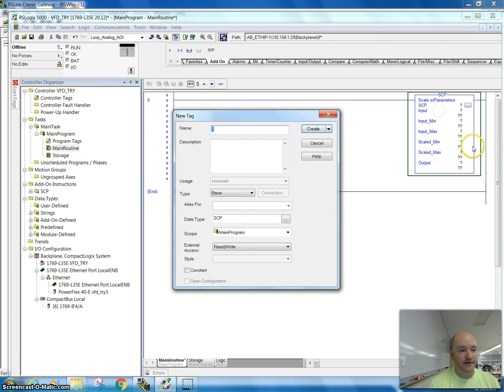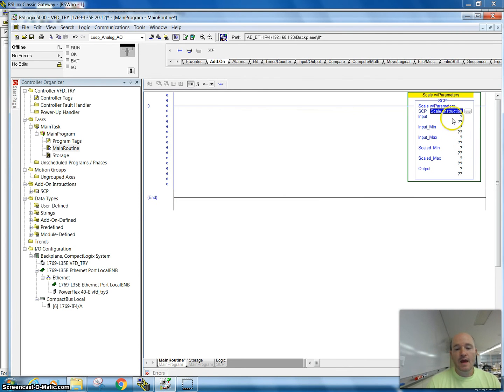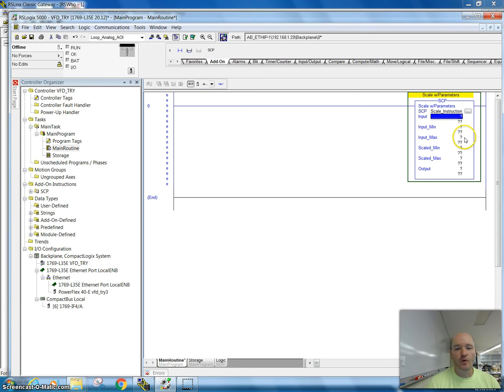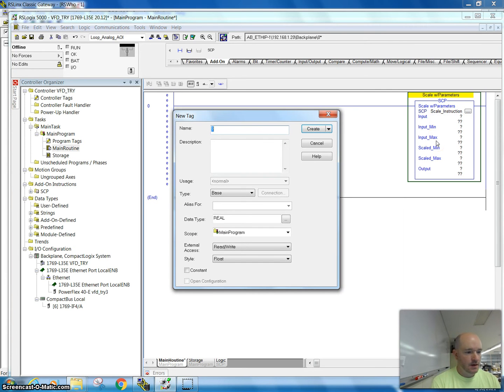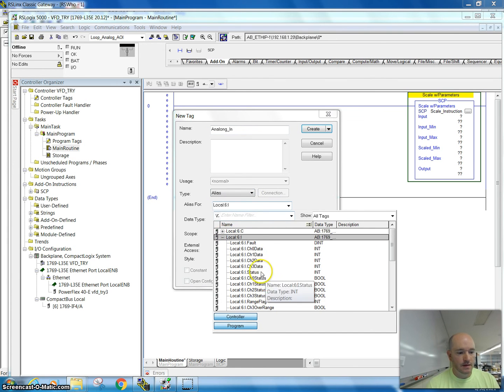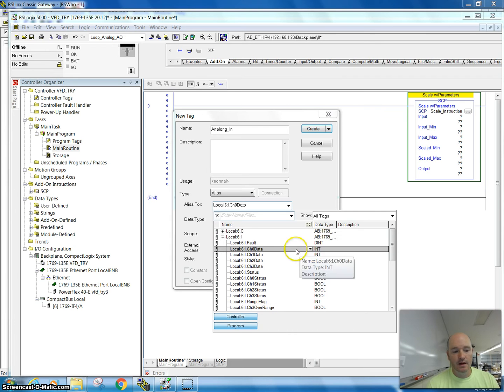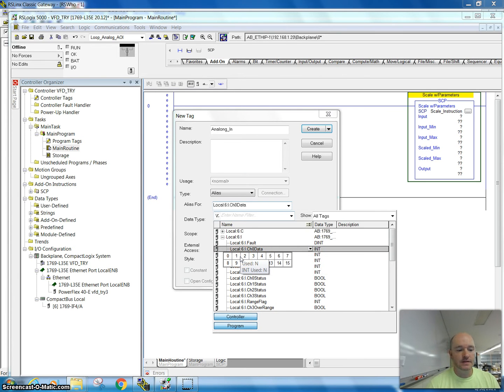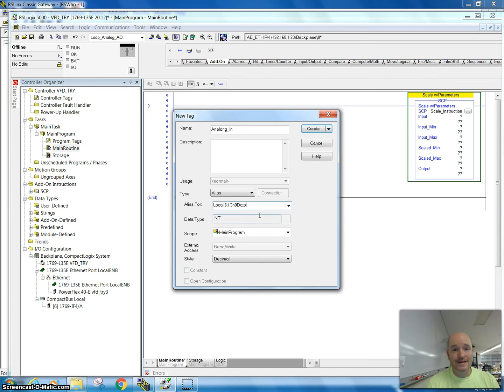The first thing we have to do is create a tag for this — I'll call this 'scale instruction'. Then we need an input. The input we're going to use is an analog input tied to slot 6, channel 0, and I'll show you that when we get online. We're using a 4 to 20 milliamp signal. I'll select new tag, change this to an alias, grab the input, and this is going to be my channel 0 data. I don't want to go to the bit level since it's an analog signal — I want to stay at the data level, so you're at the int level, because of how many bits it's able to give you. We'll hit create and that will come in.